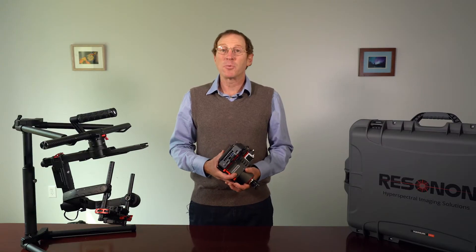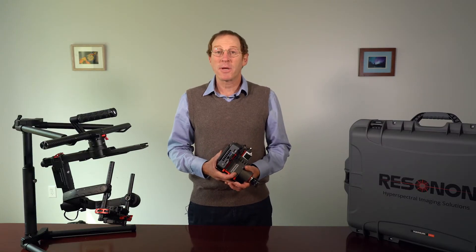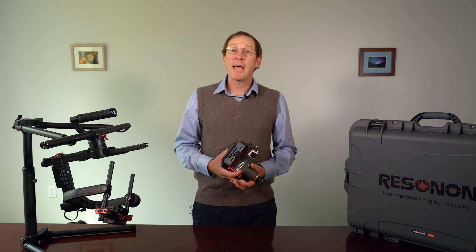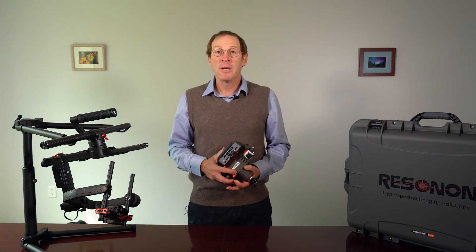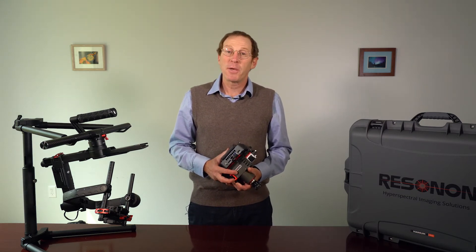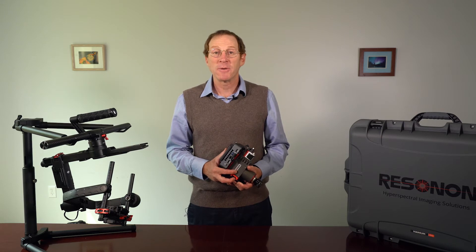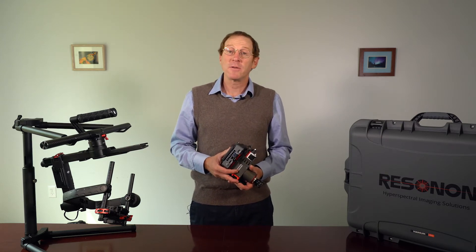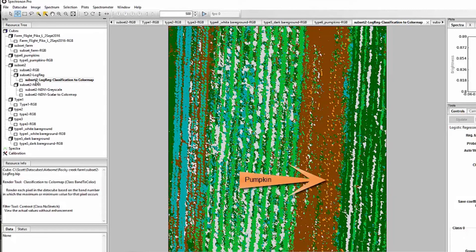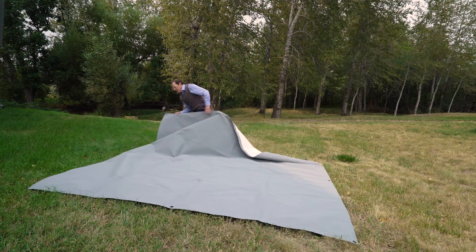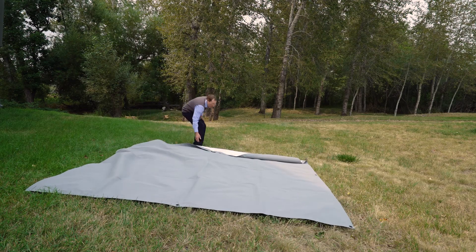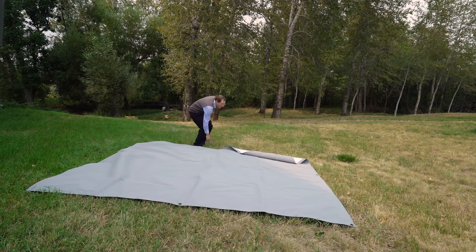The imager comes with radiometric calibration data which is the absolute response of the imager in both the spatial and the spectral dimensions. This data is used to convert raw data to radiance and this process can be performed using Resonon's Spectronon software. The system also comes with a calibration standard to convert radiance to reflectance.